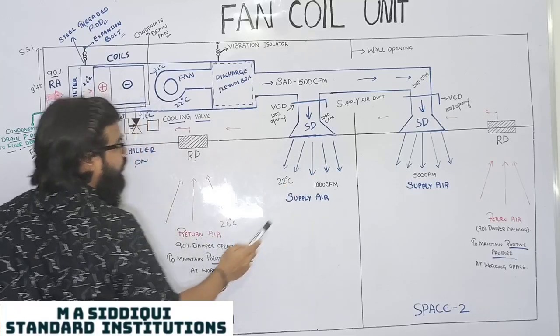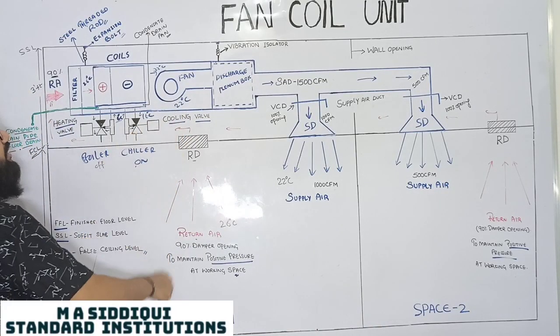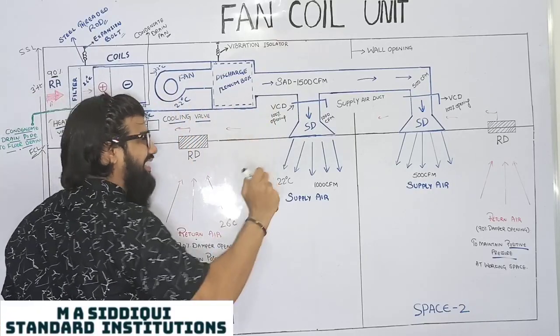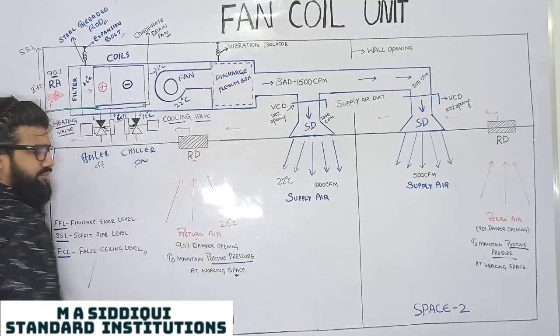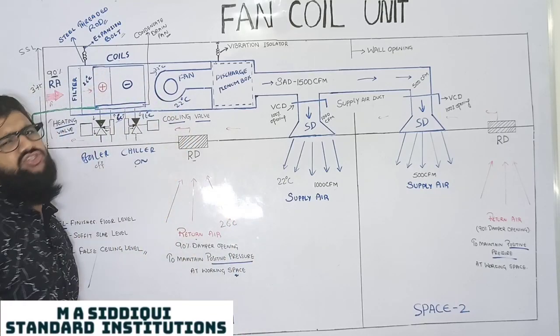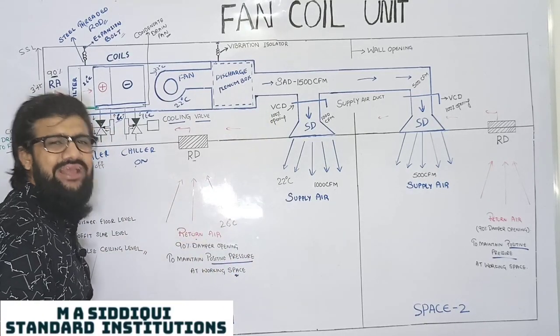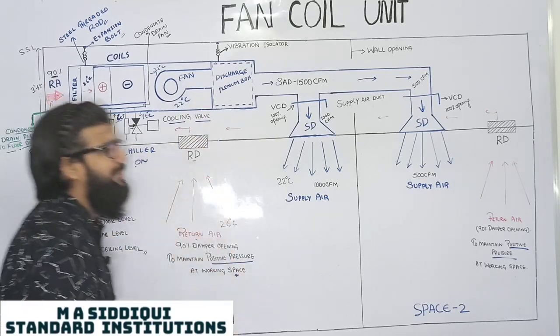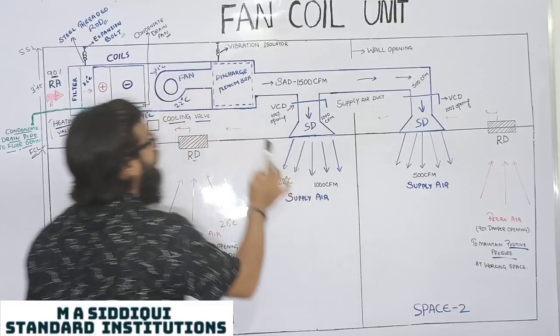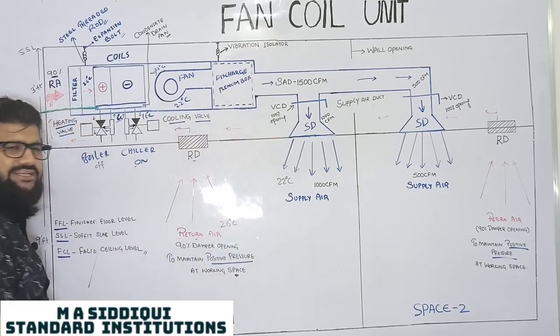This conditioned air is again given back to, as a supply air to your space 1 and to your space 2. This FCU is of capacity 1500 CFM. This 1500 CFM blower will blow the air at a rate of 1500 CFM from your discharge plenum box. Discharge plenum box is used for proper circulation of air without any frictional loss, and such that the mouth of fan blower and the mouth of duct should be equally arranged properly.